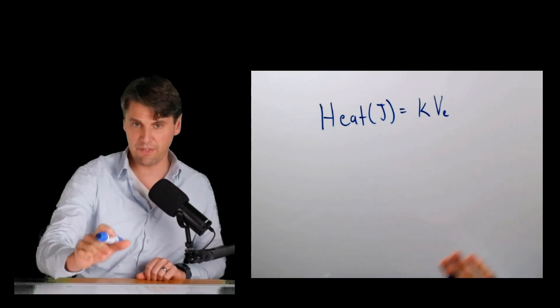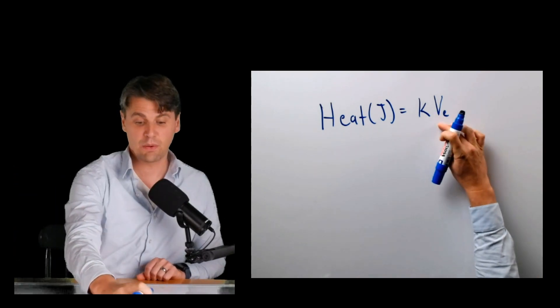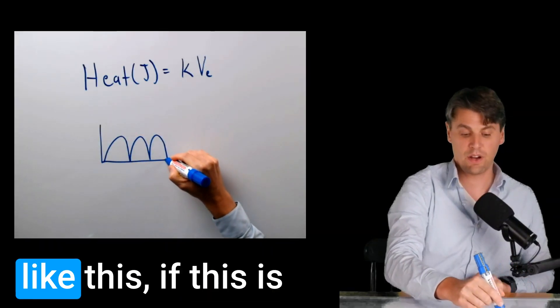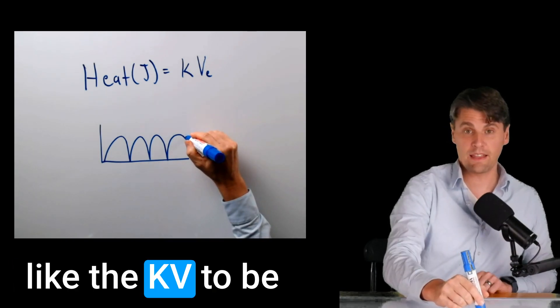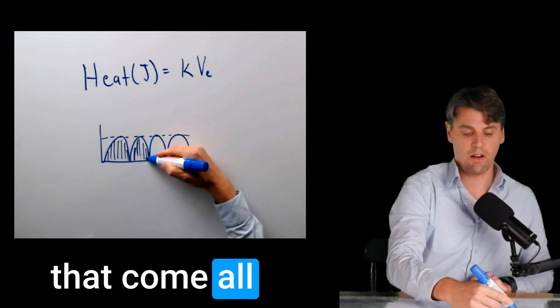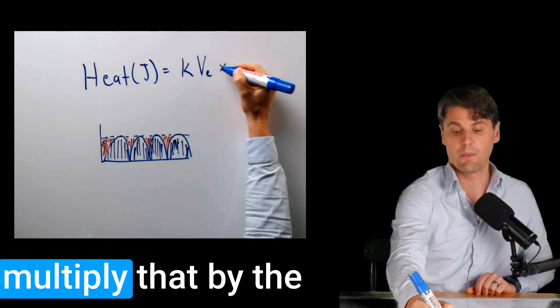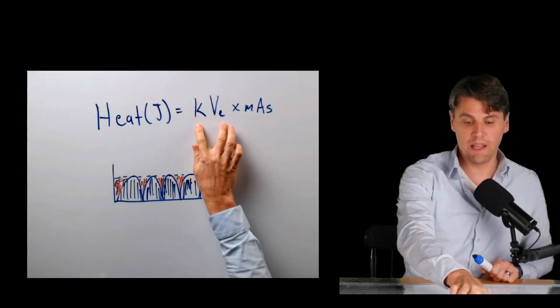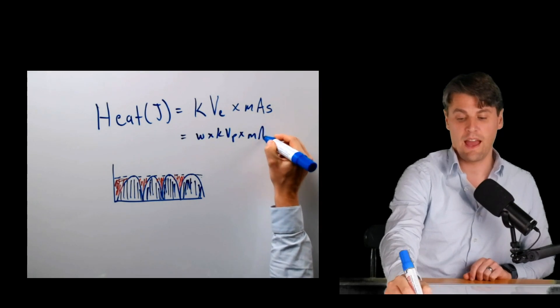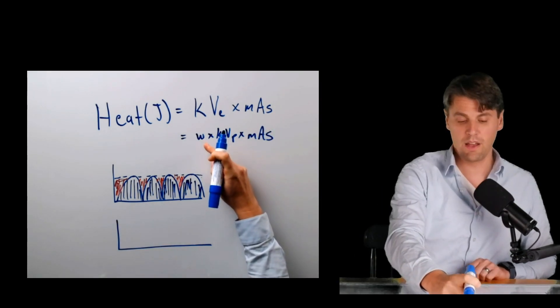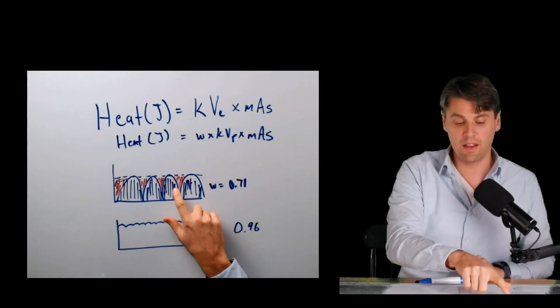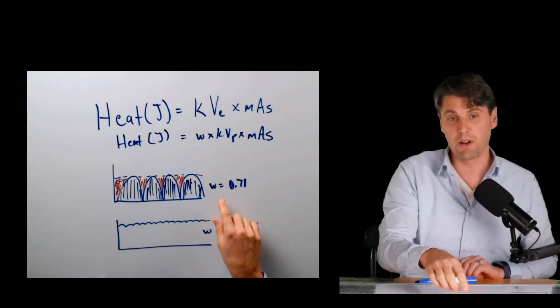If our KVP was perfect, if it was a nice flat KV, then this would just be the KVP, but this is the KV effective. If we have a full wave rectified circuit, we would like the KV to be right here, but what we actually have is KVs in this range that come all the way down and back up. We can break this down into W, a weighting factor, times the KVP times the MAS. You'd like W to be close to one. If it's a nice perfect system, W is one. For the case of full wave rectification, W is 0.71. The blue areas in comparison with the red areas determine what W is, so that's 0.71.